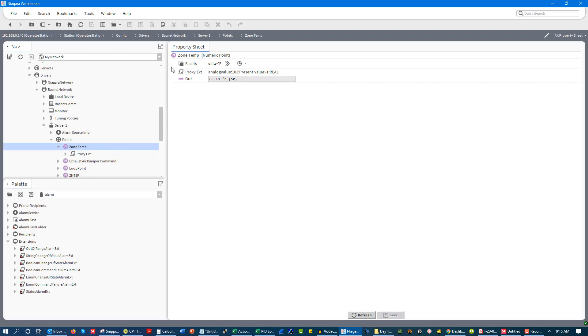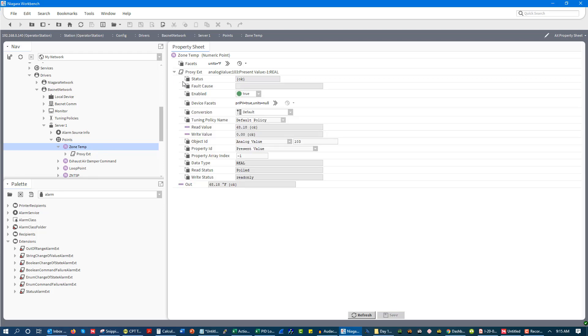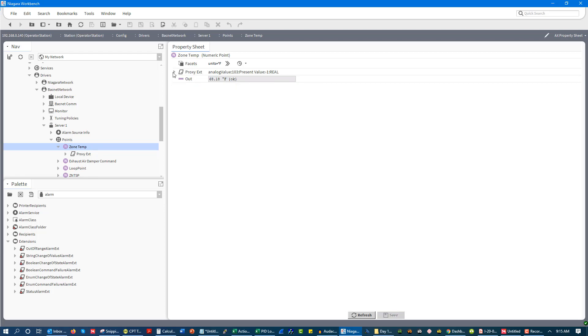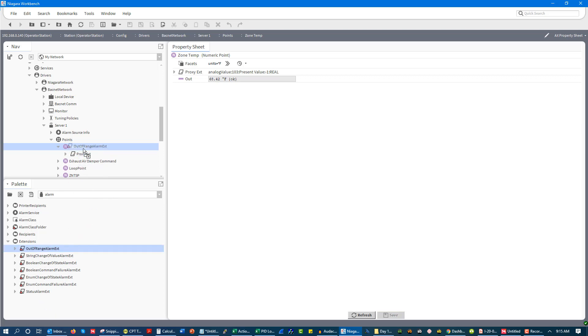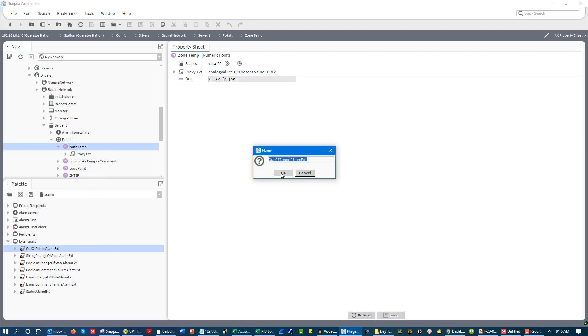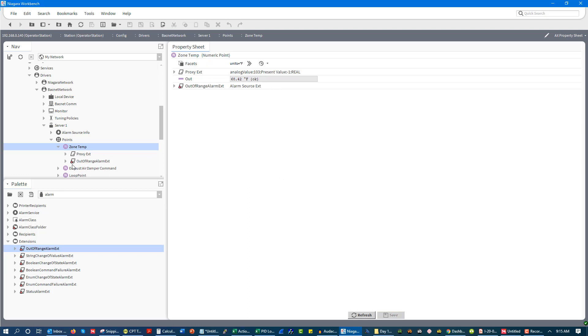The point itself does not have on this software necessarily an alarm. Like if I click on it, we see it doesn't really have an alarm. Now in some other software, like if I were to open up GFX and we were to click on a physical point, they actually have the ability to have the alarm in the point. But for this, I use an extension. So what I would do is I would use something like this out of range extension. And so this gives me an out of range alarm extension.